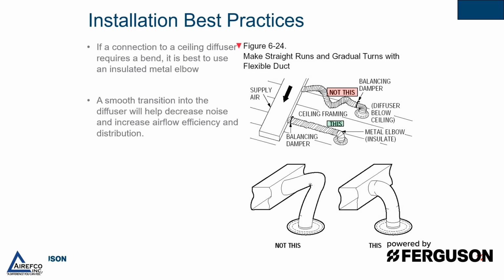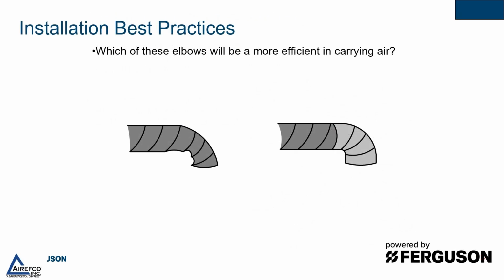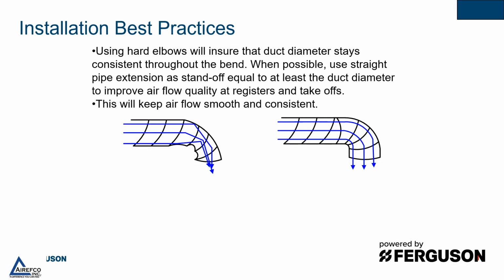If you're connecting flex duct to a ceiling diffuser that requires a bend, it is best to use an insulated metal elbow. A smooth transition into the diffuser will help decrease noise and increase airflow efficiency and distribution. Which of these elbows will be more efficient in carrying air? Using hard elbows will ensure that duct diameter stays consistent throughout the bend. When possible, use straight pipe extensions as standoff equal to at least the duct diameter to improve airflow quality at registers and takeoffs. This will keep airflow smooth and consistent.